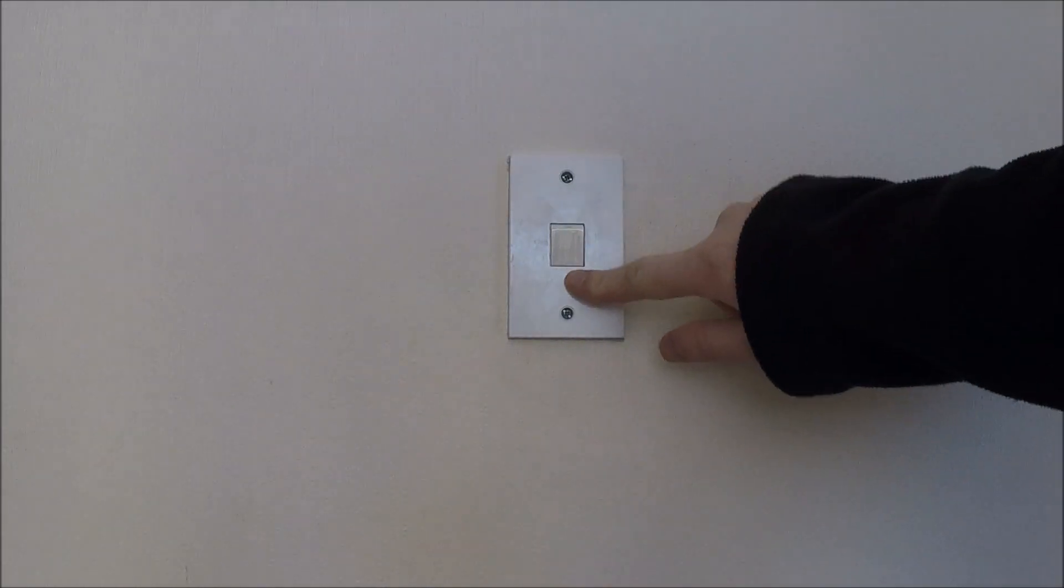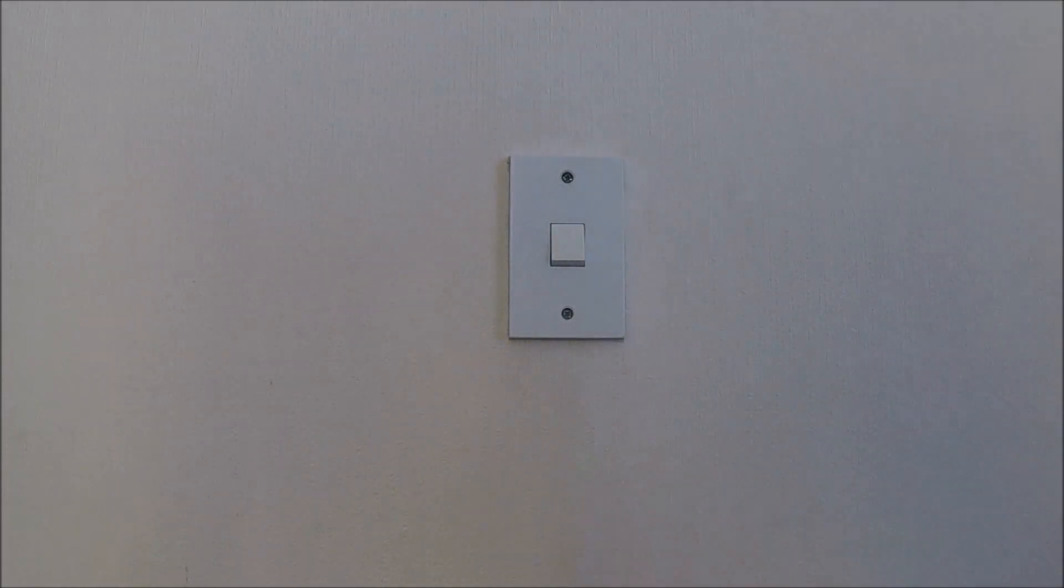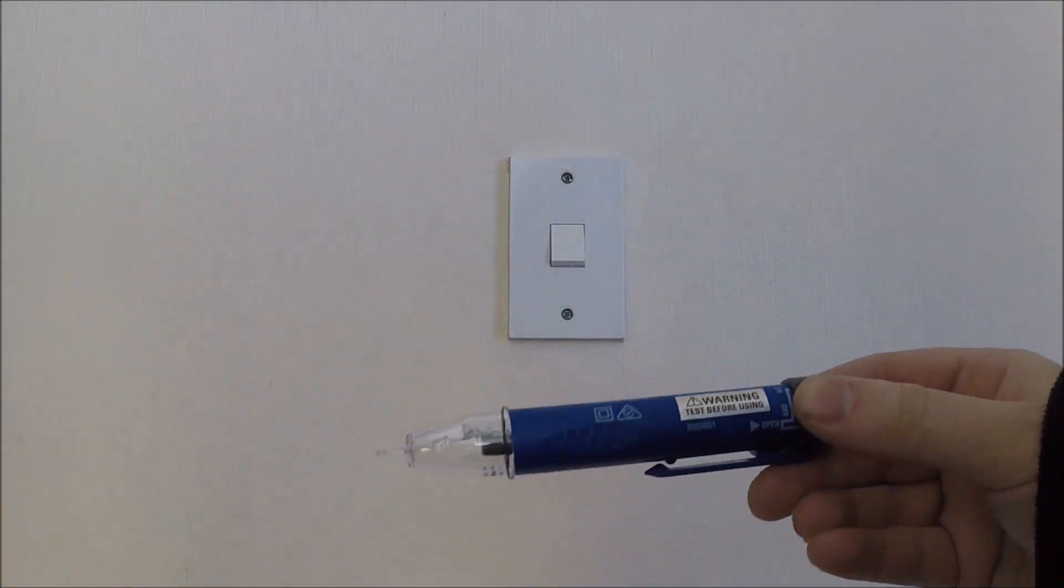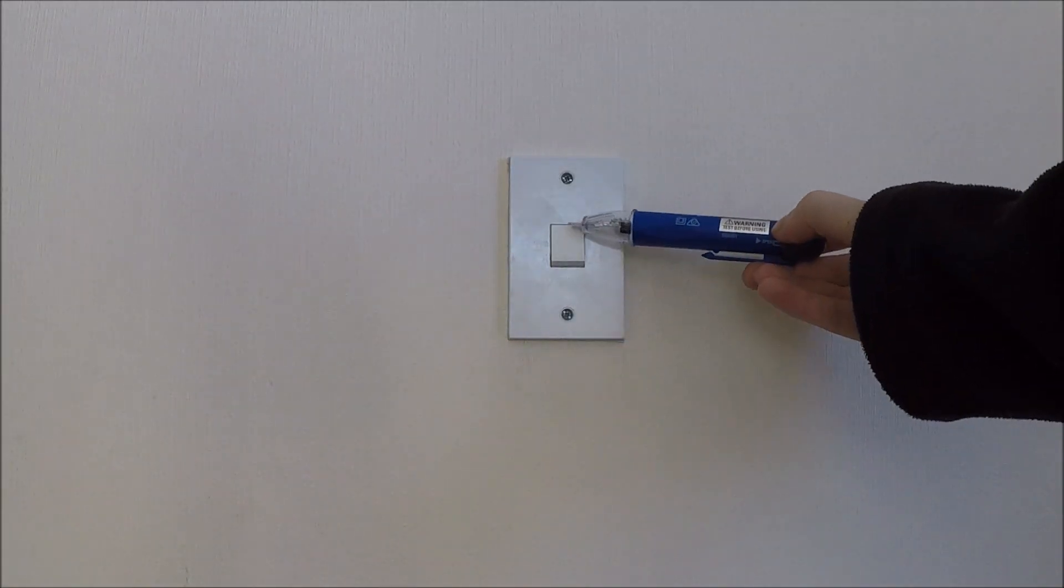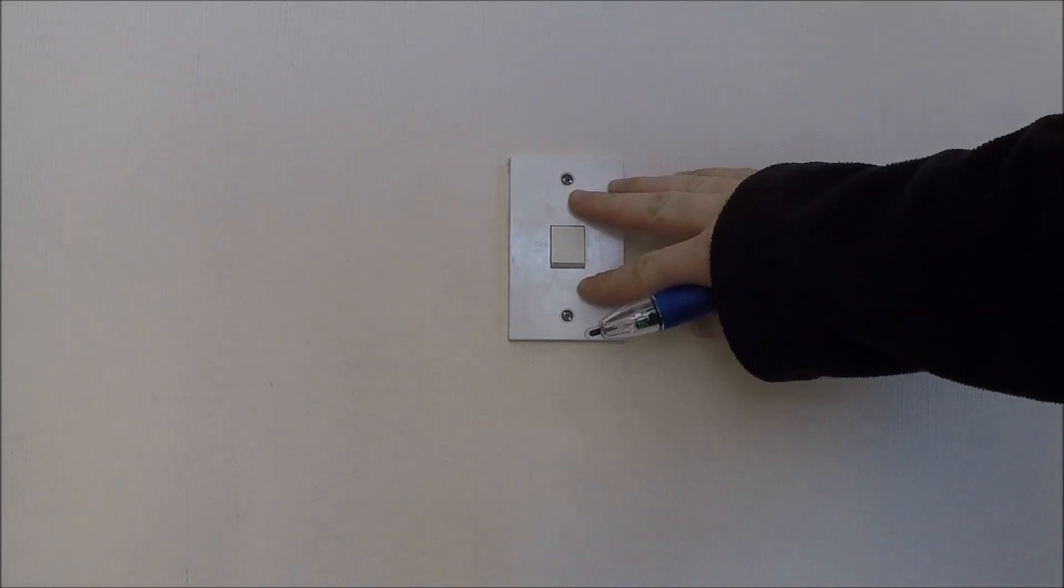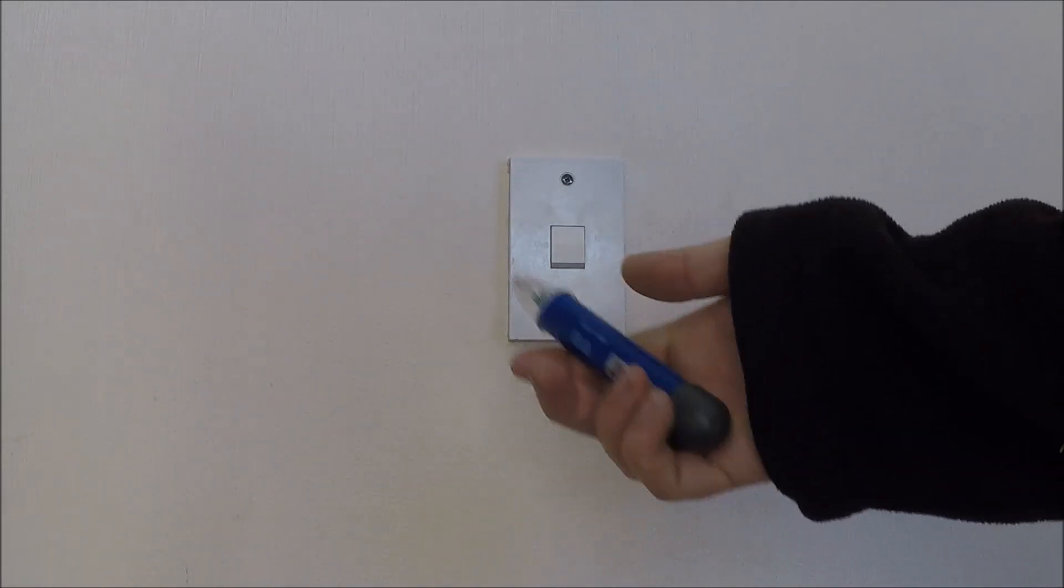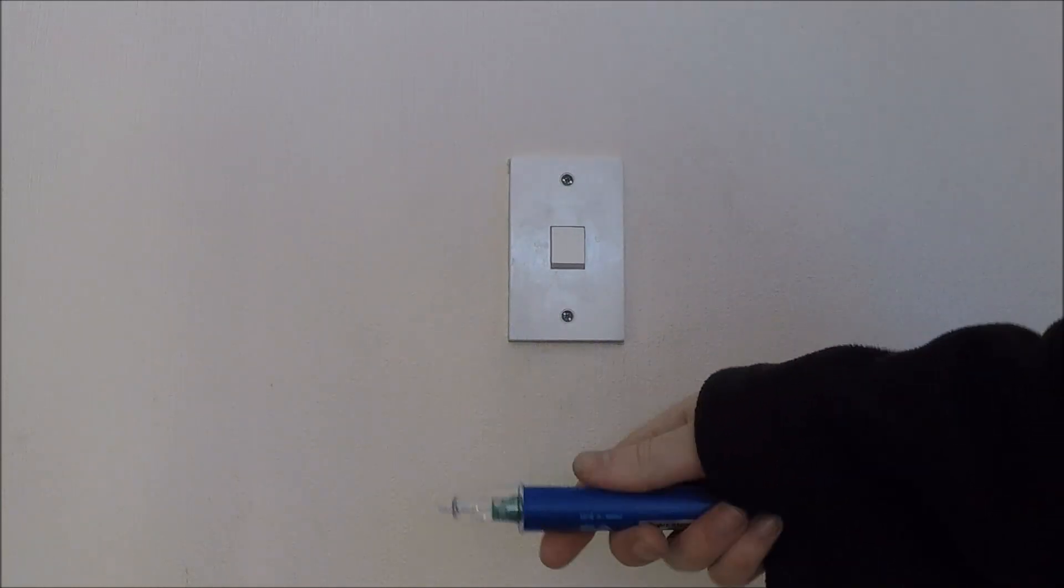Now the first thing I've done is isolated the power to the switch. So it does nothing. And we test that by using a volt stick. Turn it on. No power on it. Also test the cables behind the light switch when we pull it off with the volt stick before we touch them.